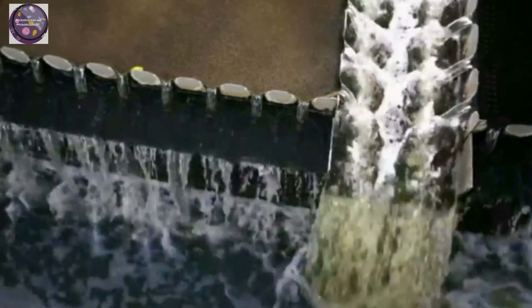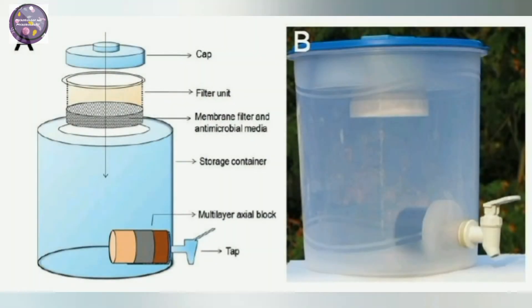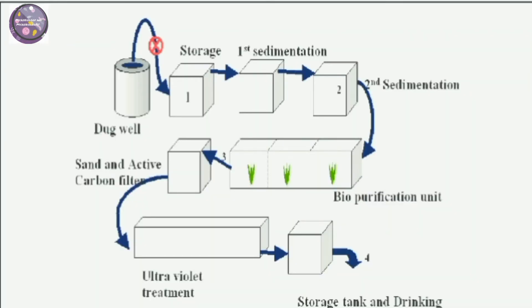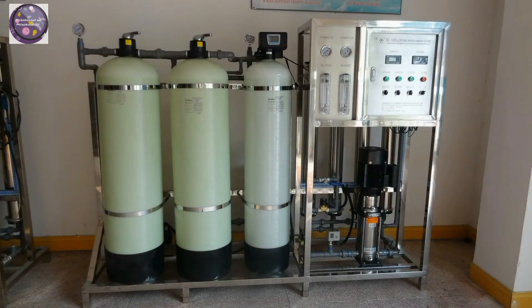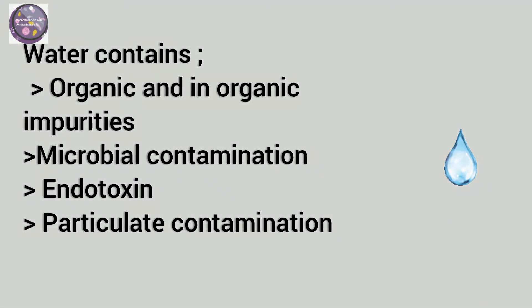Water is an important raw material in GMP and in validating the manufacturing process. Why is purification of water important? Although tap water is reasonably pure, it is always variable due to seasonal variations and regional variations in quality. One must remove impurities and control microbes to avoid contamination of products. Pre-treatment depends on the quality of feed water, and water quality should be specific for product quality. Purification may be necessary because water can contain organic and inorganic impurities, microbial contamination, endotoxins, and particulate contamination.